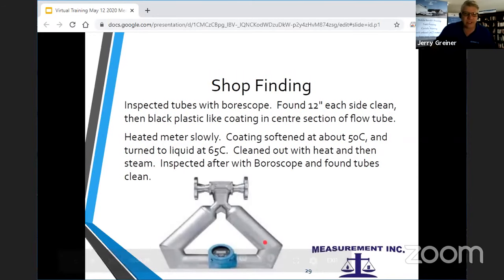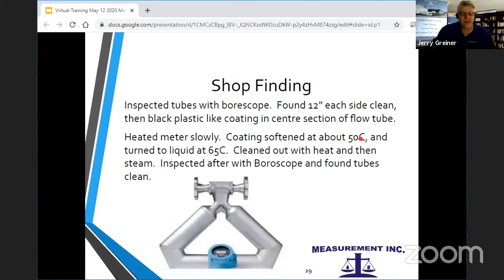We weren't really sure how to get these out, but Coriolis meters are good for a standard temperature of about 240 Celsius or so. So we thought we'll just heat it up and see what happens. When we heated it to about 50 degrees Celsius, it turned soft, and at 65, it just turned to a liquid. So we just tipped it upside down and turned it out. As soon as it hardened on our cloths, it looked like just black plastic. It melts at about 65 degrees Celsius, it cools off, and it's black plastic. After we got it out, we checked with the borescope and found the tubes all the way clean throughout.